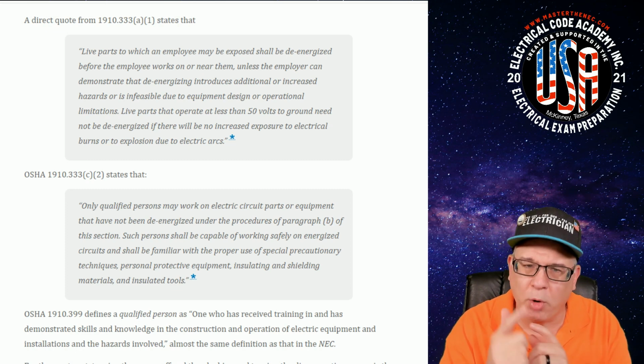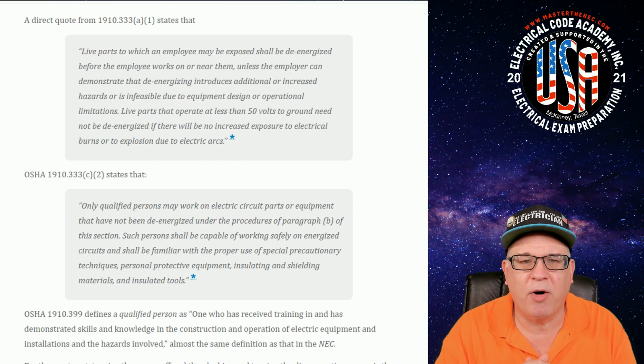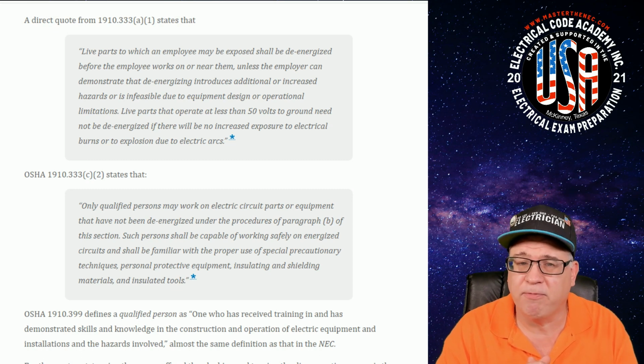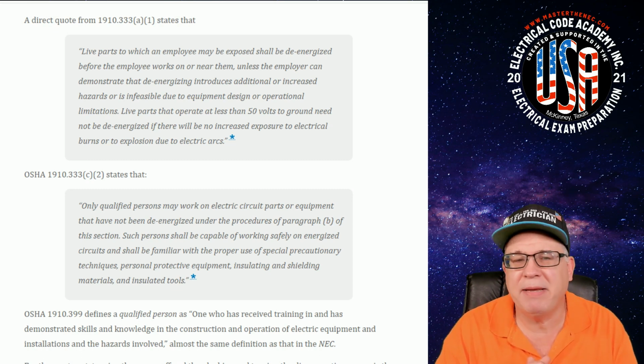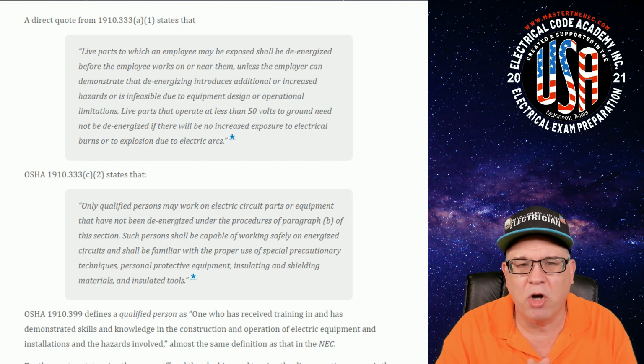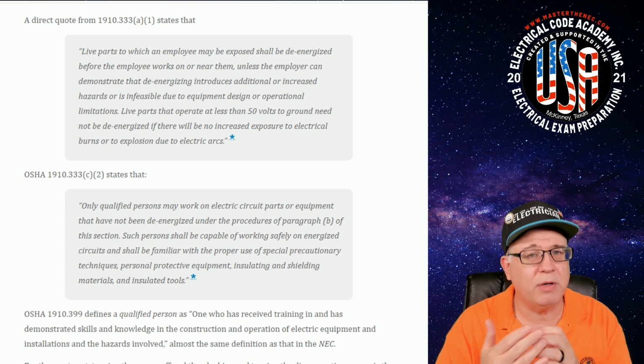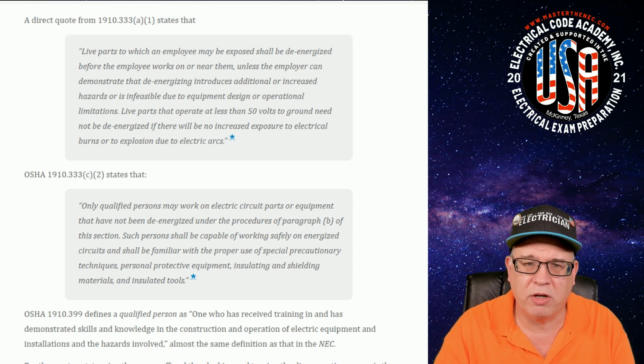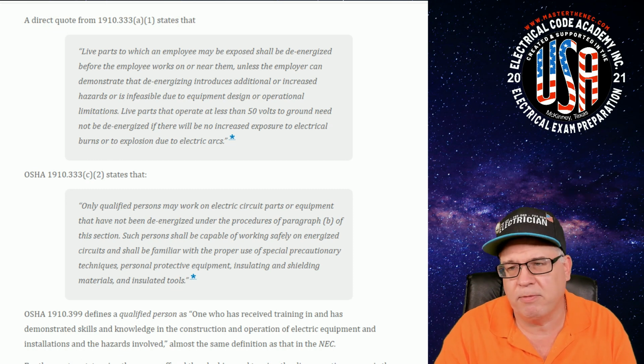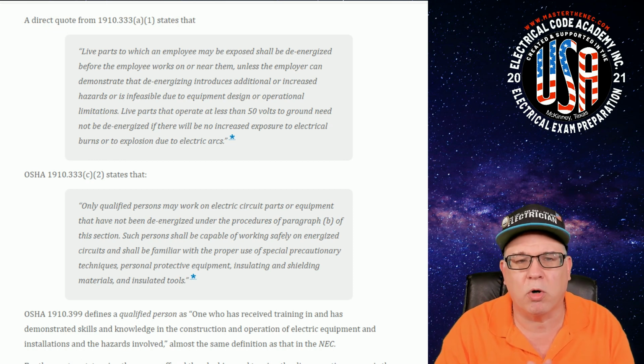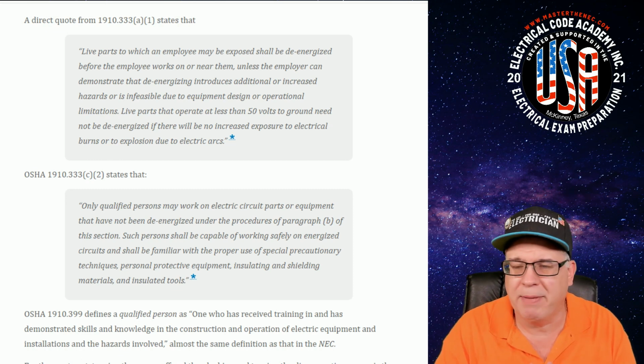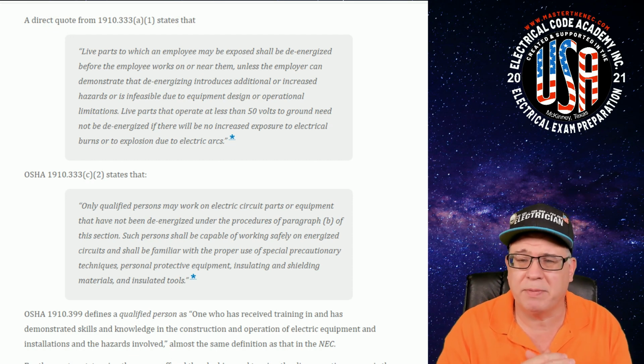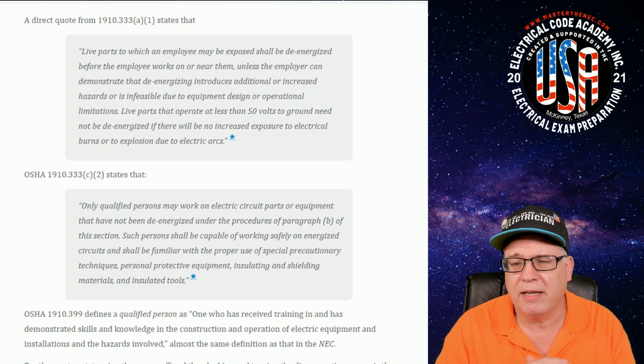Now, continuing to read: live parts that operate at less than 50 volts to ground need not be de-energized if there will be no increased exposure to electrical burns or explosion due to electric arcs. So you'd have to do an evaluation of the condition if you're dealing with something less than 50 volts to ground. Then you might be able to work on that without worry. One example of this would be a doorbell circuit, things like that.